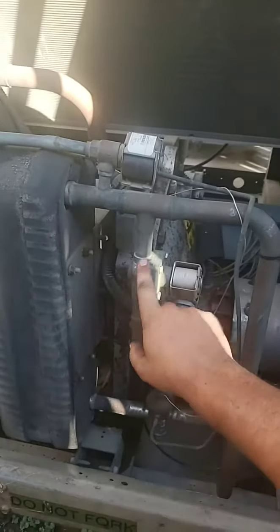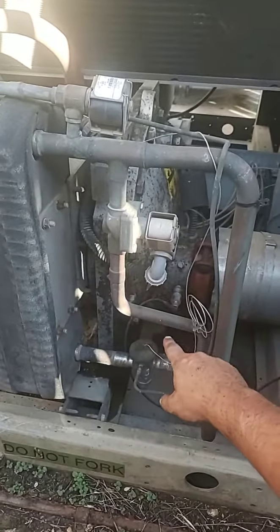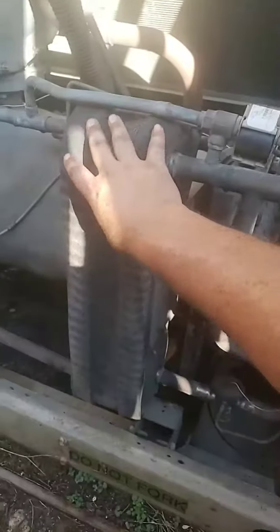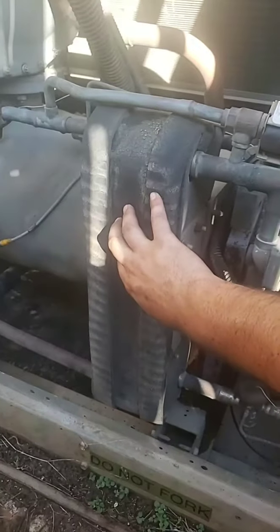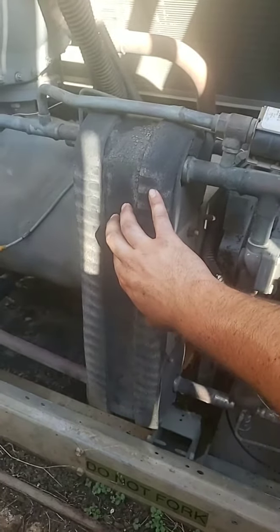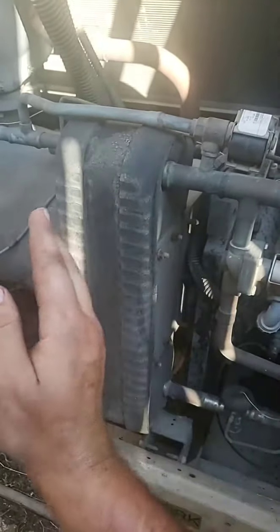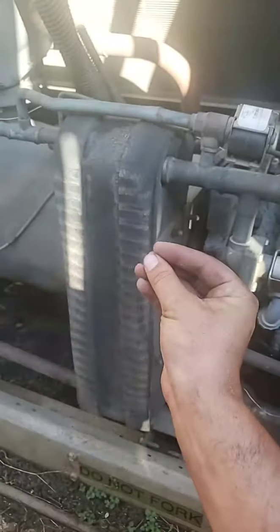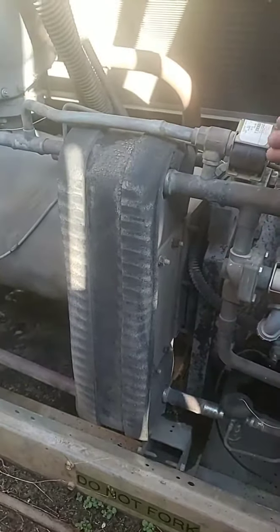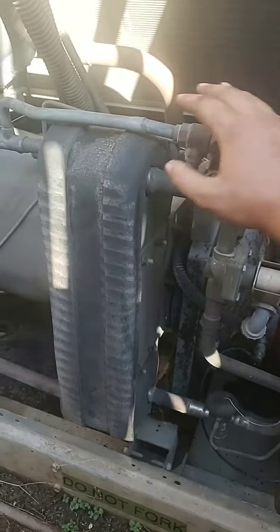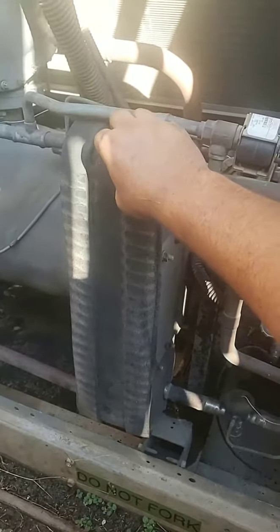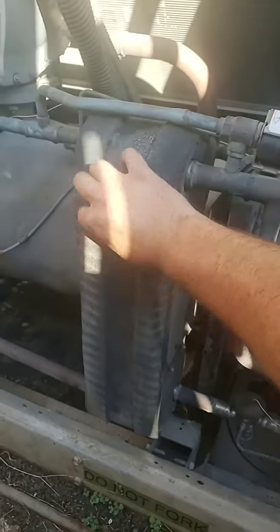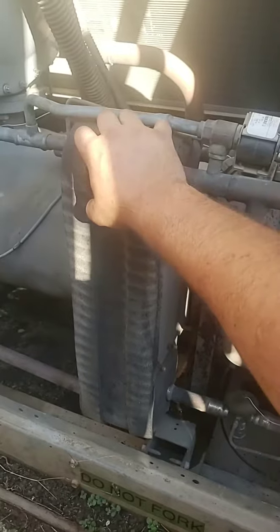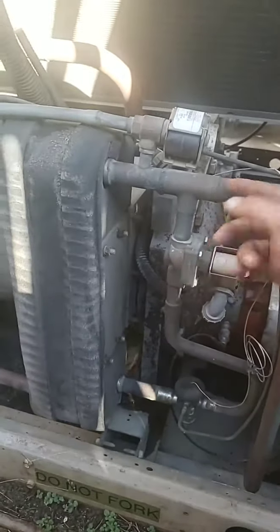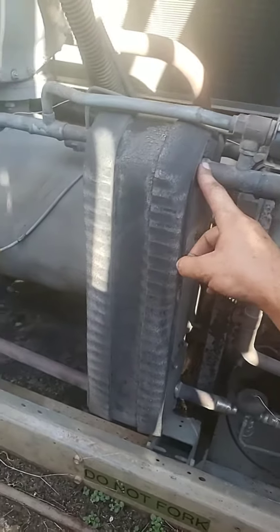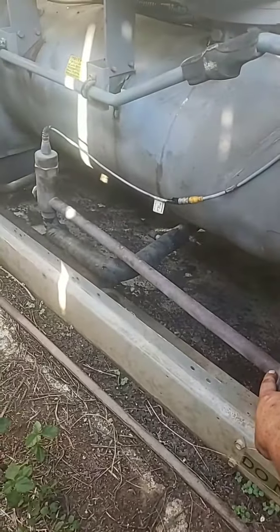This T coming off here with a solenoid, this is your economizer. Okay, so all this, this whole insulated black piece, this is a brazed plate heat exchanger. And with a brazed plate heat exchanger, you've literally got multiple plates that are brazed together with internal chambers. Now, the thing to keep in mind is there are 2 separate circuits inside of this heat exchanger, and those circuits do not mix. But because of how they cross over each other internally, they do a very good job of exchanging heat. So what's happening here is the liquid is actually coming into the heat exchanger here and back out down here to our EXV.